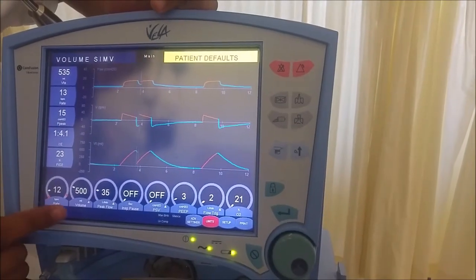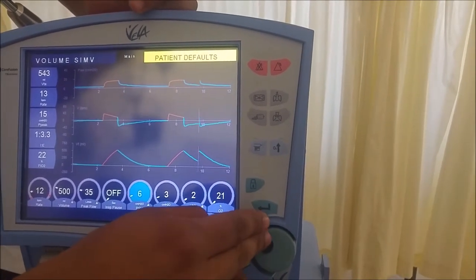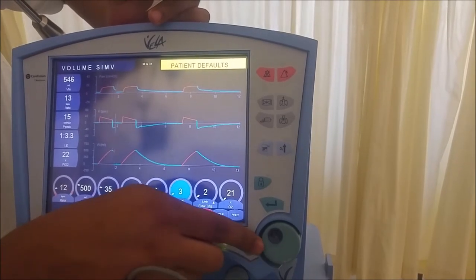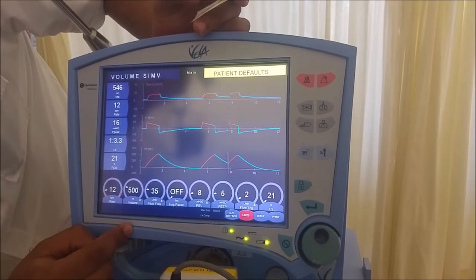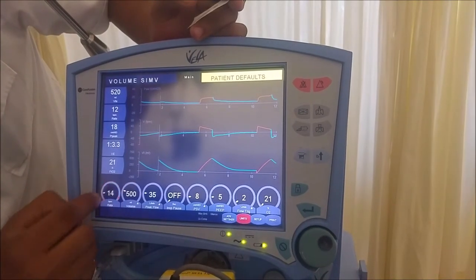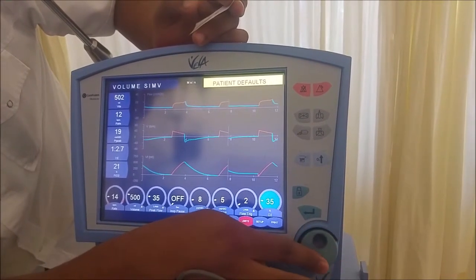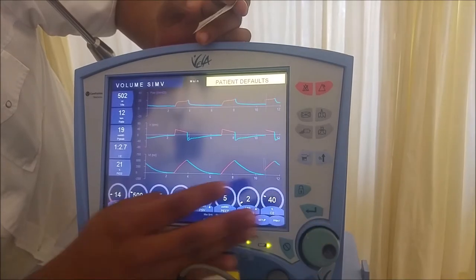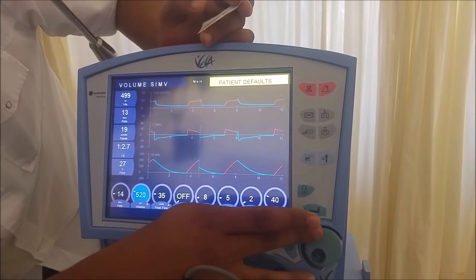Volume SIMV mode delivers three types of breaths: the mandatory, or controlled, breath, which is the breath delivered by the ventilator according to the settings; the spontaneous breath, which the patient initiates and completes on their own; and the synchronized, or assisted, breath, which is when a spontaneous and controlled breath coincide. Example settings for volume SIMV are a tidal volume of 550, a respiratory rate of 14, PEEP of 5, FiO2 of 40%, and a PSV of 8. The values used in this mode, and the following two, are an example and will have to be adjusted according to the patient's profile.